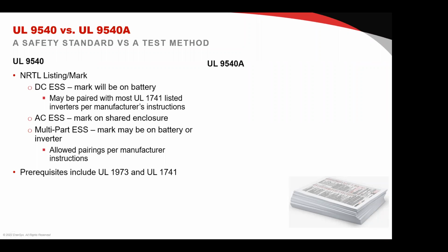So again, the prerequisites include a UL 1973 listed battery or a UL 1741 inverter. And these listings, the UL 9540 listing, in addition to IRC, it's also required by NEC and most stationary energy storage system products. So you're pretty much going to have this if you're getting your job permitted and inspected. This will be a requirement.